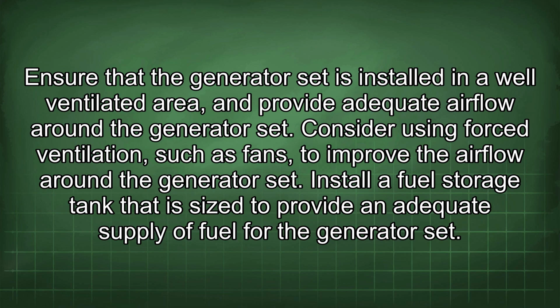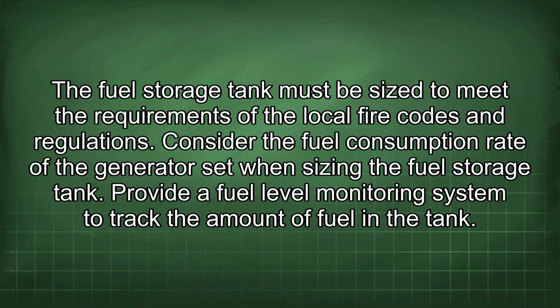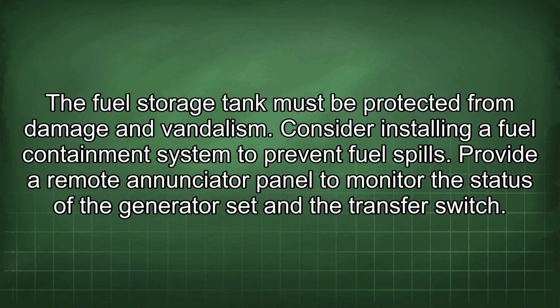Install a fuel storage tank that is sized to provide an adequate supply of fuel for the generator set. The fuel storage tank must be sized to meet the requirements of the local fire codes and regulations. Consider the fuel consumption rate of the generator set when sizing the fuel storage tank. Provide a fuel level monitoring system to track the amount of fuel in the tank. The fuel storage tank must be protected from damage and vandalism. Consider installing a fuel containment system to prevent fuel spills.